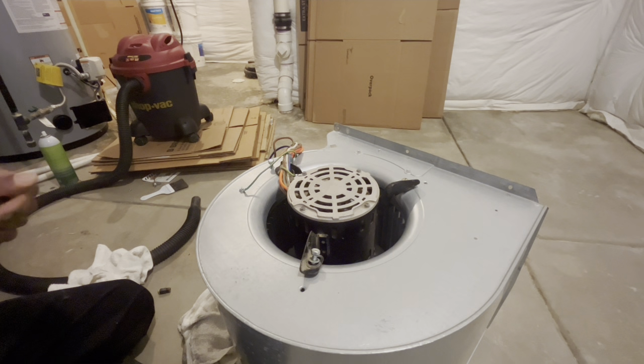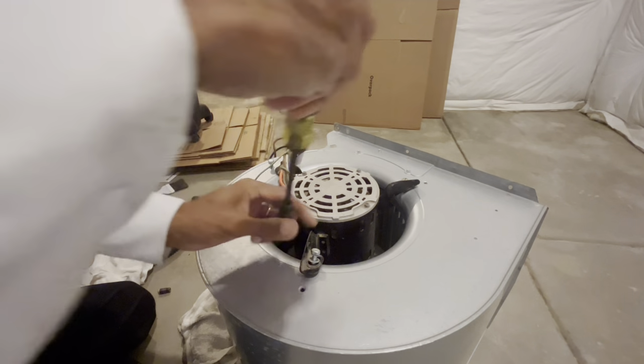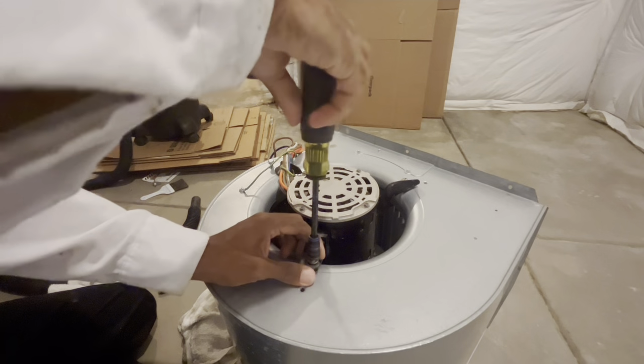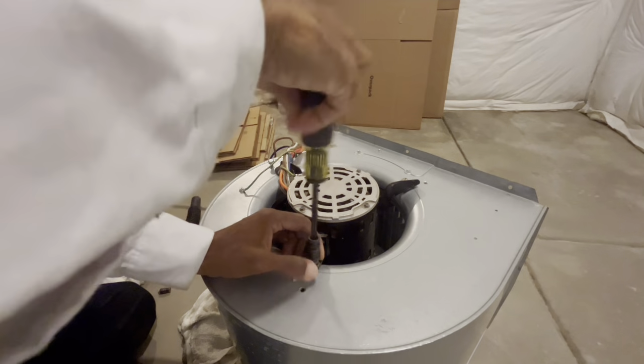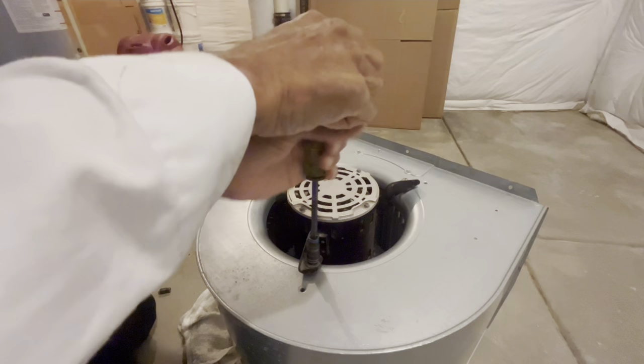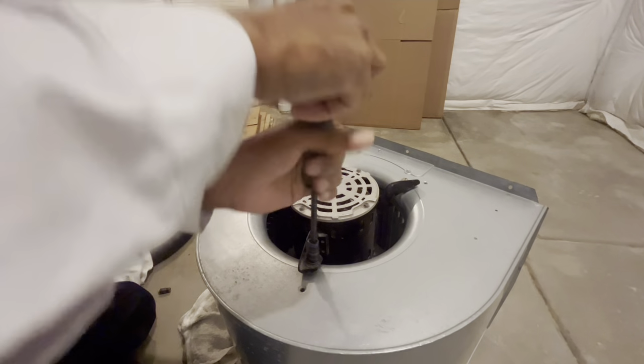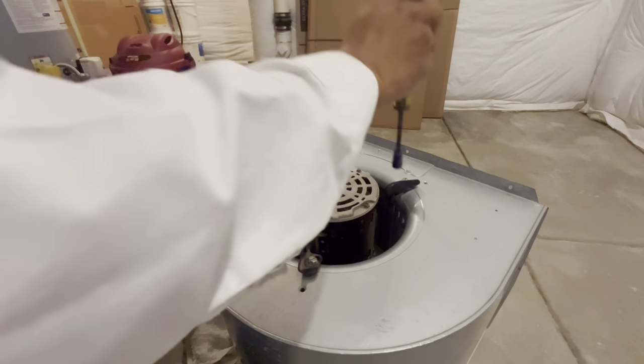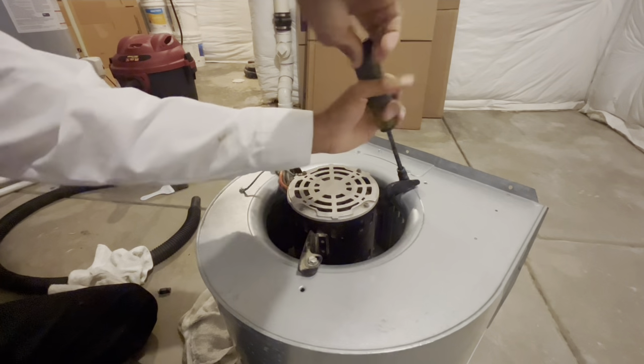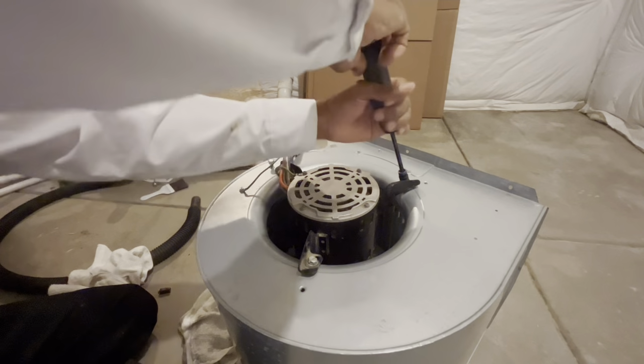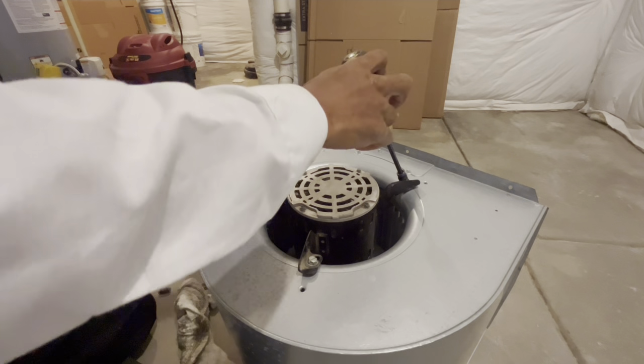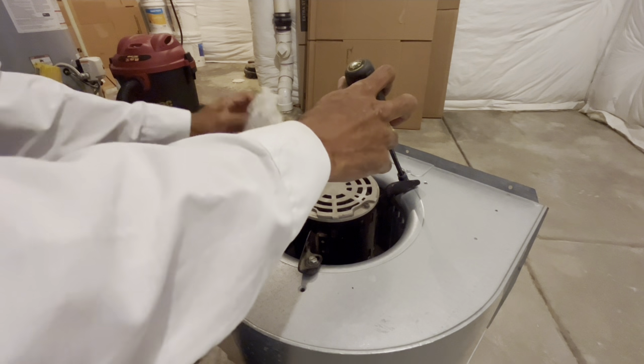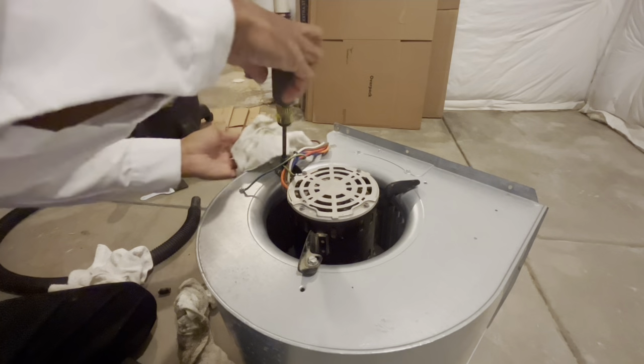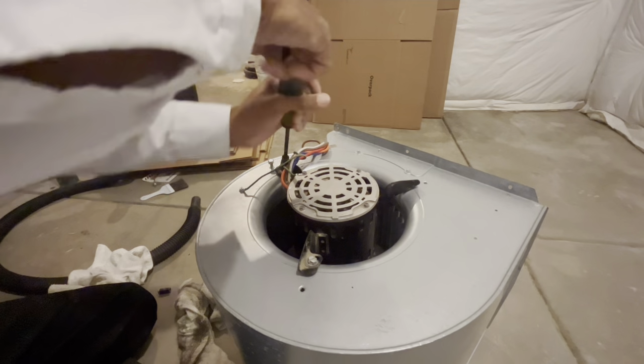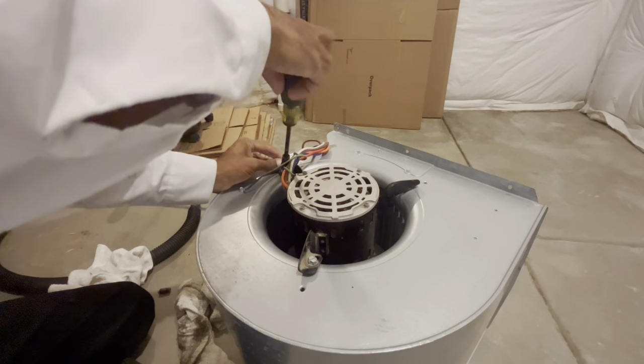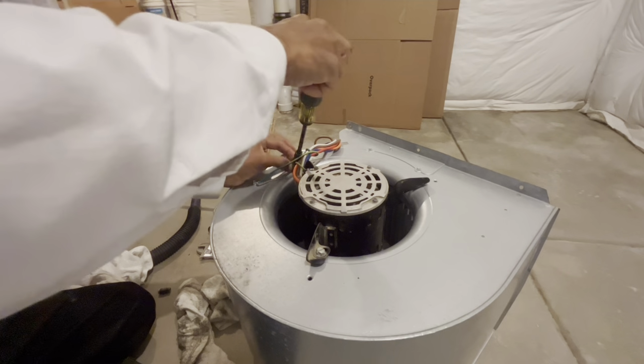So, now taking that motor, I've cleaned the shaft hole out of the blower wheel with a wire brush and taking these 3/8 inch bolts and putting it back on the housing. And whenever you do put the blower motor back on, you got to make sure that the wiring for the blower motor is in the right direction, because it has to come towards the front of the furnace. If the wiring is going towards the back, then it may not reach and they may not be long enough. Then you'll find out by the time you actually slide it all together, put everything back together, that the wires are not long enough. Then you have to take everything back apart.